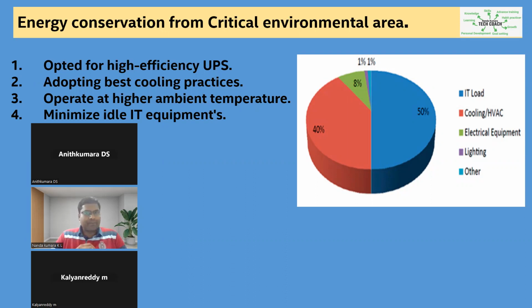I strongly recommend that if any conventional type UPS has above 17 to 20% losses, you straight away recommend it to your management, or you can take the initiative and replace it with a higher efficiency UPS. Even today's UPS has eco mode, which we call energy conservation mode. That means the loss will be almost nil, zero. The power goes straight through the UPS, but the UPS operation will be minimal. Using that kind of high efficiency UPS, we can reduce the 8% losses, which is measurable and achievable.